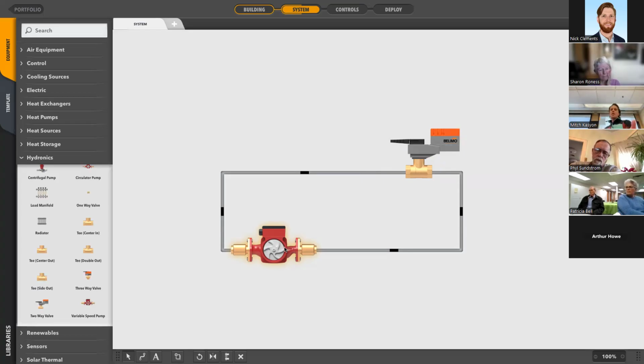So what I mean is in this simple loop, we know as engineers that when the valve is in a closed position, we don't want the pump to be on because we're just going to deadhead the pump and not get any flow. By defining these pieces of equipment in Quantum and establishing a connection between them, our control engine is coming to those same conclusions.